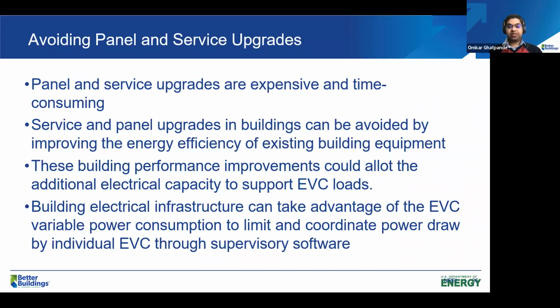But these panel and service upgrades are very expensive and time consuming. Building performance improvements could be done instead, improving efficiency of other building components to allow additional electrical capacity for these EVC loads. A supervisory control can also be used to monitor and control power consumption of EV chargers, which is useful to limit overloading on the circuit.